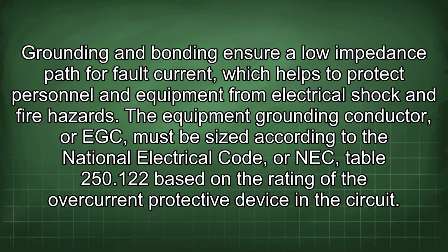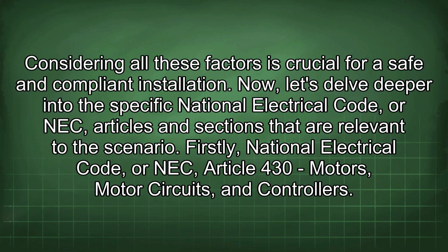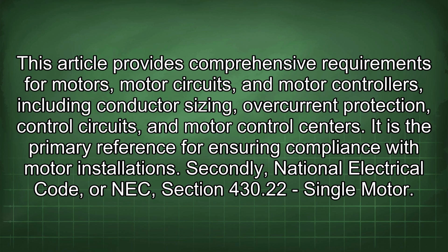The equipment grounding conductor, or EGC, must be sized according to the National Electrical Code, or NEC, Table 250.122 based on the rating of the overcurrent protective device in the circuit. Considering all these factors is crucial for a safe and compliant installation. Now let's delve deeper into the specific NEC articles and sections that are relevant to the scenario. Firstly, NEC Article 430 Motors, motor circuits, and controllers. This article provides comprehensive requirements for motors, motor circuits, and motor controllers, including conductor sizing, overcurrent protection, control circuits, and motor control centers. It is the primary reference for ensuring compliance with motor installations.